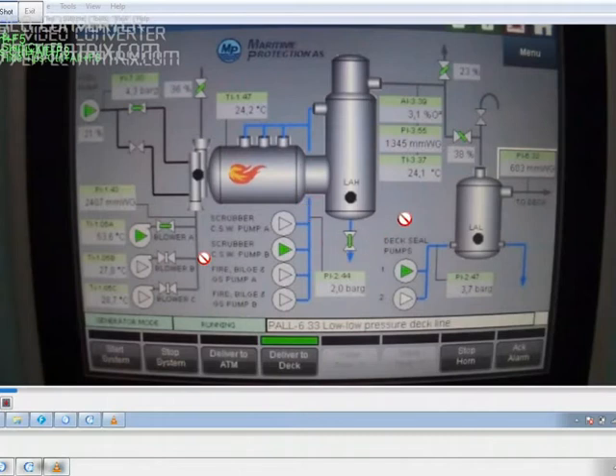By taking rounds, if you see this valve is fully open and the fuel pressure here is maybe 16 bar, that means the system is not working properly.